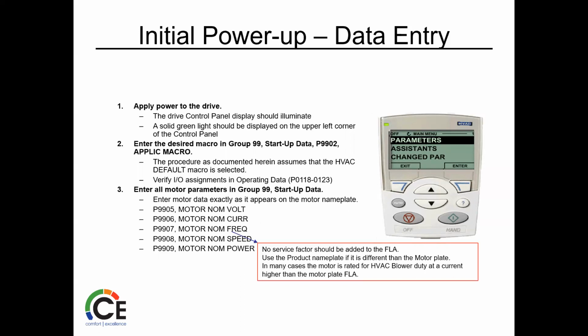So initial power up, obviously we're going to turn the thing on, right? No service factor should be added to the FLA, so we're not worried about any of that. Use the product nameplate. It's determined on the motor plate. In many cases, ready for HVAC blower duty at a current higher than motor plate FLA. So it just means sometimes the parameters may be a little different than what the motor is.